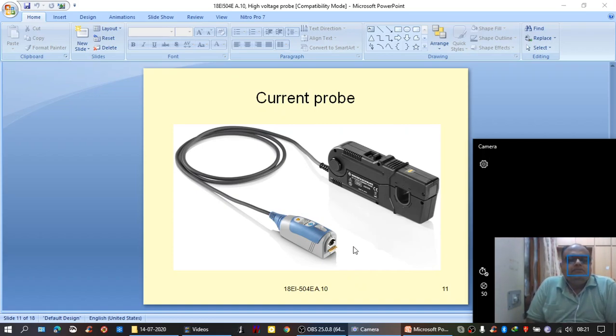This current probe, actually how do we measure current? Normally we measure current in a circuit by opening the circuit and placing the meter in series, a normal ammeter. But here by using this type of probe, that is current probe, we need not open the circuit. Simply we have to place the wire through which the current is flowing in this slot in the clip. And when this cable is connected to a meter, the meter will give the readout value, the current value. That is how a current probe is used.